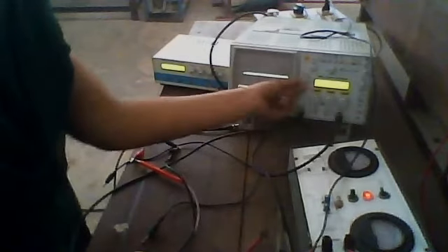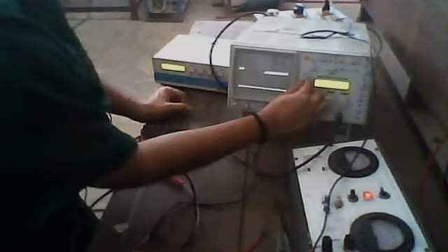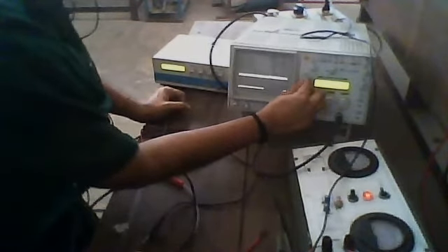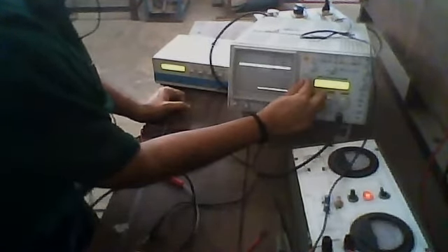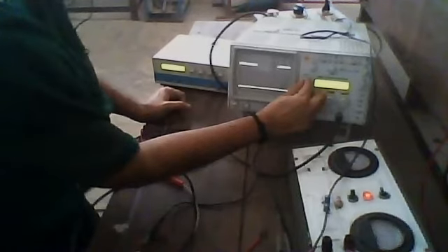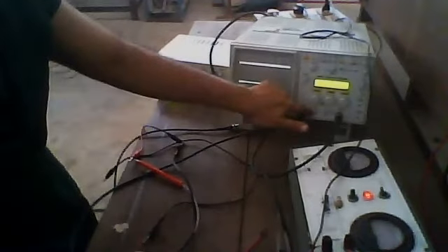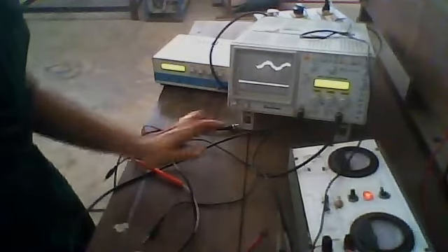When you adjust the first Y shift, you can see this axis moving up and down. So now you can set the axis at a proper area to view the waveform. And another one can be changed by using this knob. Now you set the other axis here. Now release the ground to display the waveform. Similarly, both the waveforms.